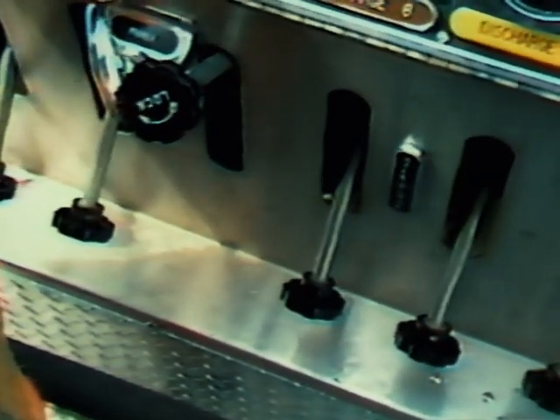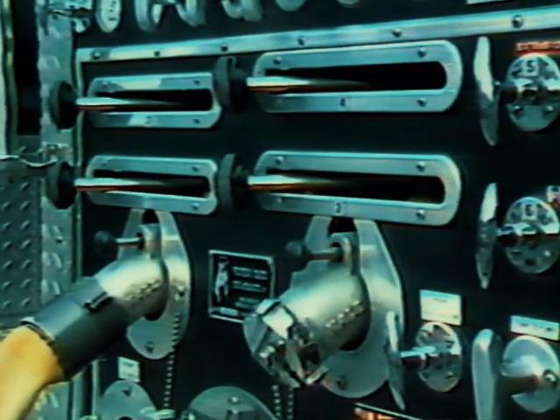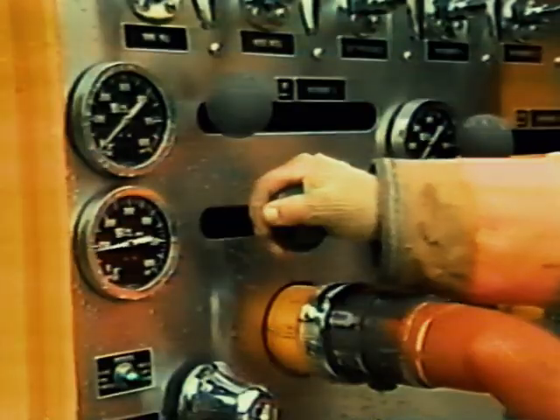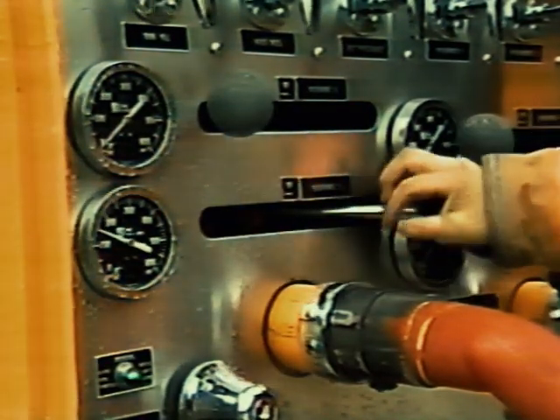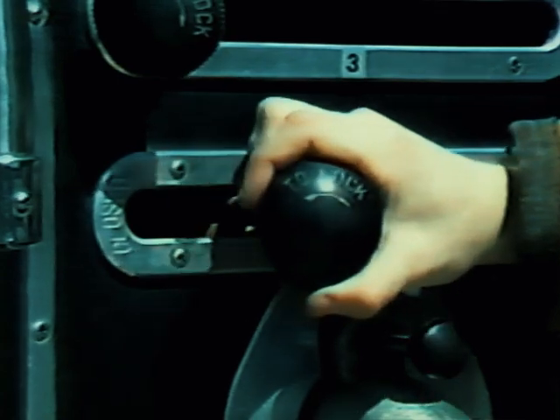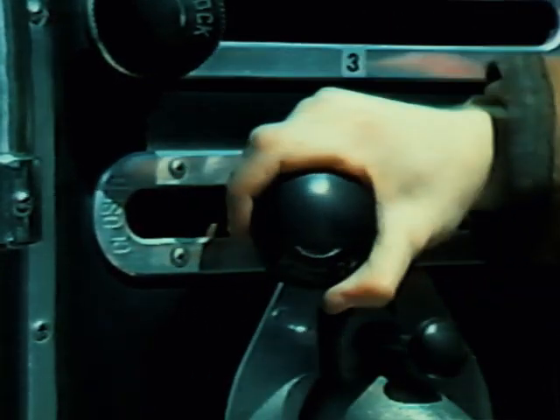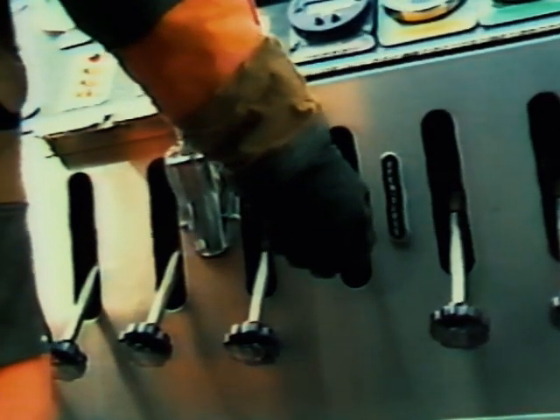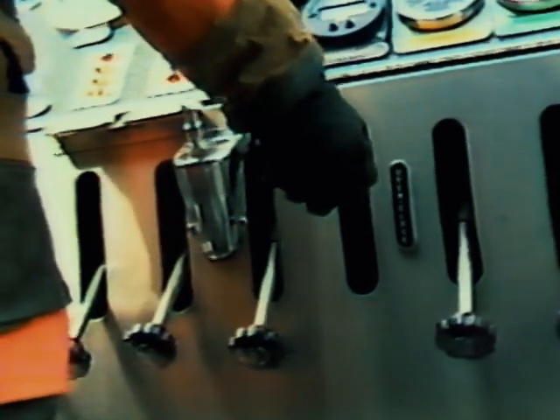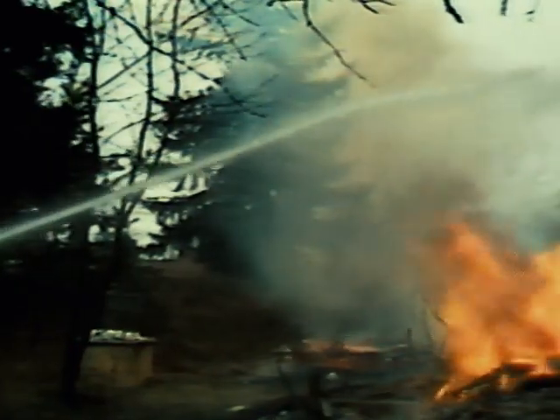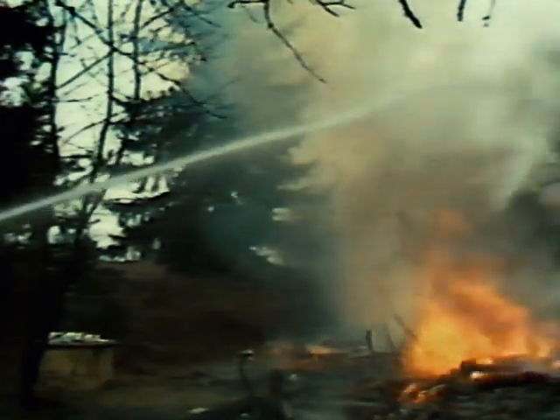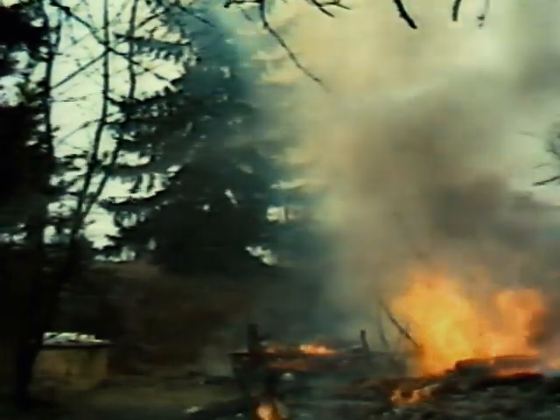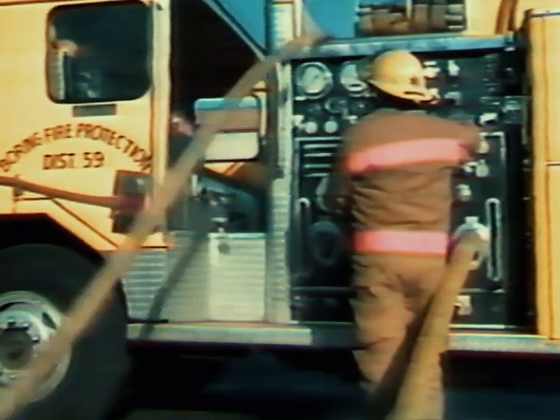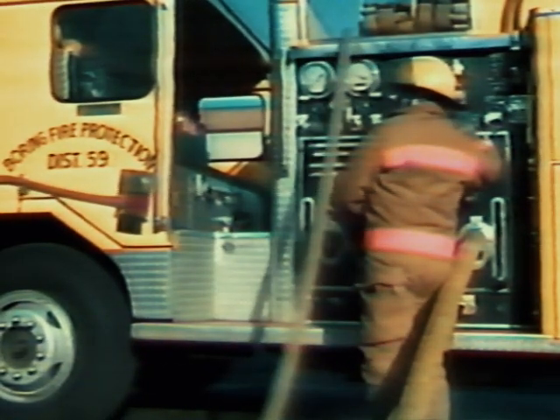Fire pumpers with up and down or side-to-side valve operation have quarter-turn valves with handles that are rotated up and down or side-to-side to open and close. These valves are locked in position by turning the knob on the handle. Always open and close discharge valves that control the flow of water to the hose lines slowly. Opening a discharge valve too quickly will cause a drop in pressure to other hose lines and cause surging.